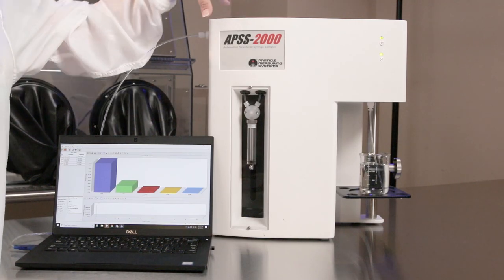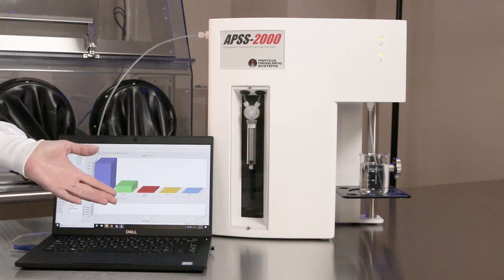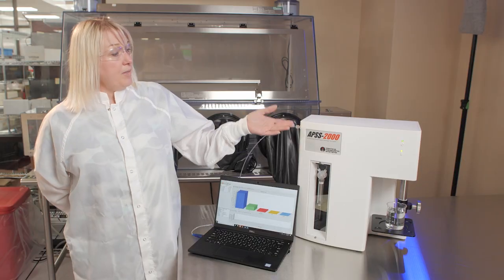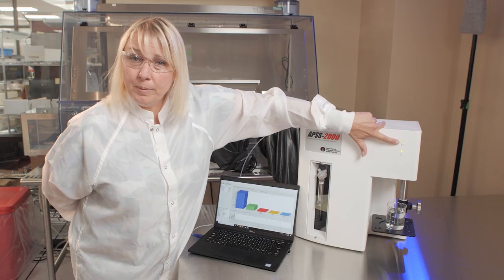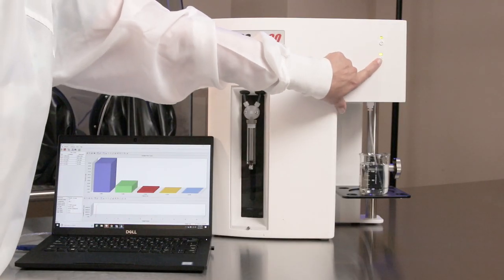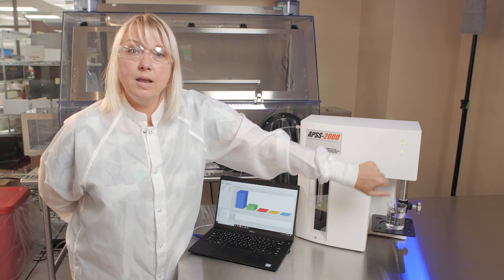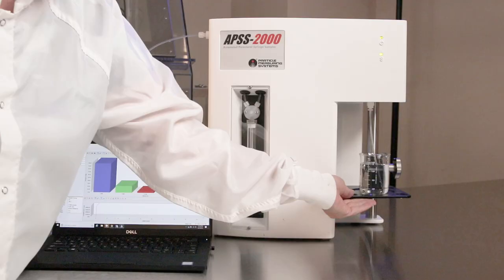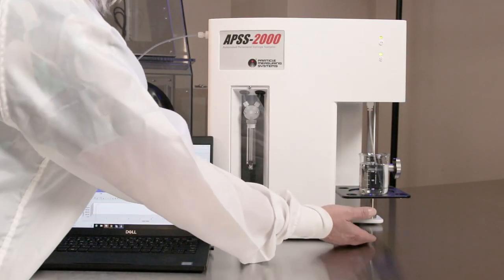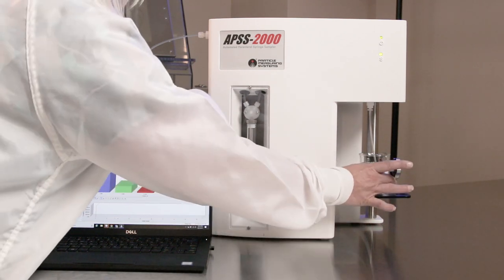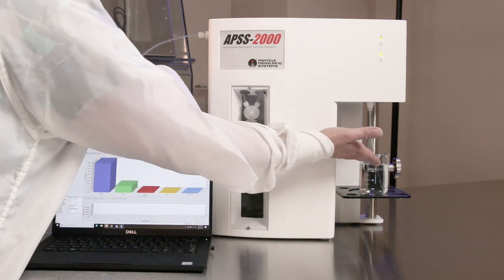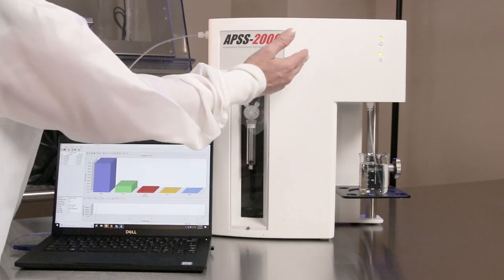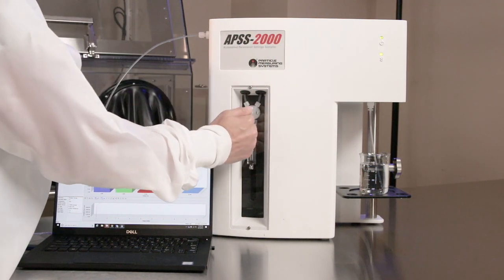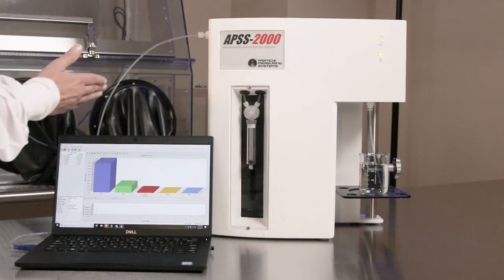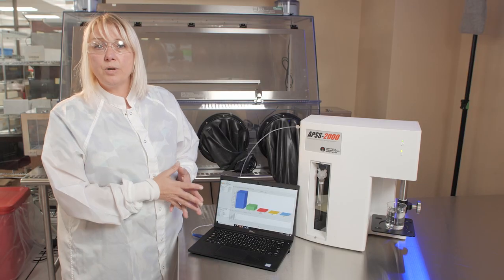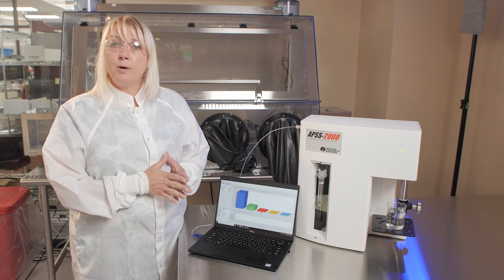There's a syringe sampler inside and the software is on an external laptop. So with the APSS-2000, we have a power button, we have a status button. When this is green, the instrument is ready. And this over here is the stand. This is an adjustable stand. This goes up and down to meet your sample. Your sample is placed here. Sample goes through the syringe, up into the sampler, down through this pump, and then out the instrument. Meanwhile, the software is recording all of the data related to non-viable particles.